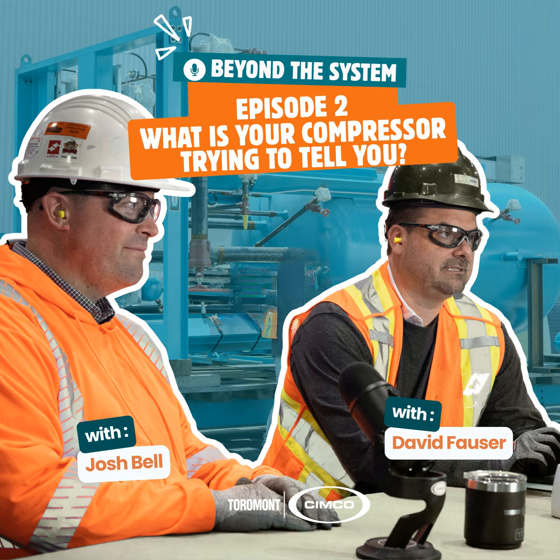I would always recommend that if you're at the point where you're going to change a bare compressor, you should at least send your motor out for rebuild. And if it's a smaller horsepower, just replace it - again, cheap insurance.